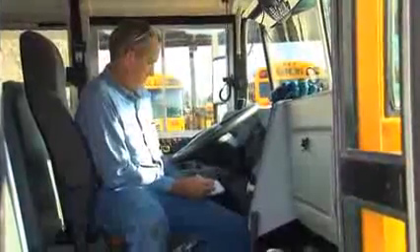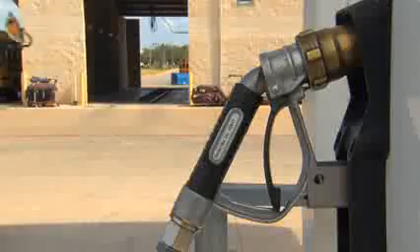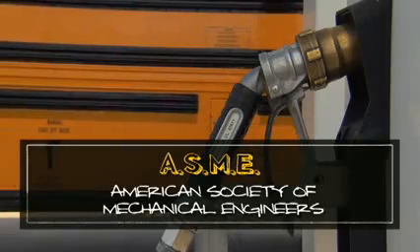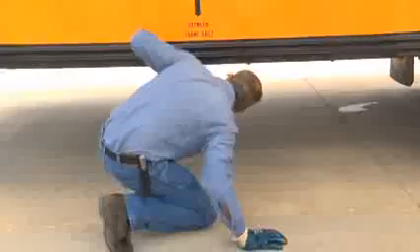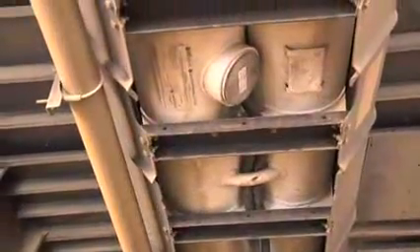When all your safety practices and preparation are set, you are ready to dispense propane to fuel a bus. The first step is inspection. Motor fuel tanks are built to ASME specifications — the American Society of Mechanical Engineers. Before you fill an ASME fuel tank, it should be inspected. Look for any leaks or visible damage to the school bus' tank, valves, or service lines, and listen for any signs of leaking. Once the fuel system has been inspected, you can refill your vehicle.